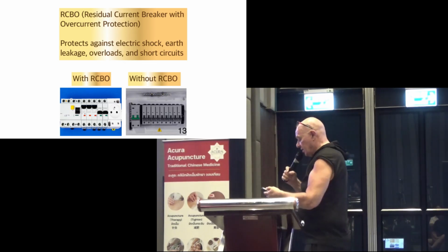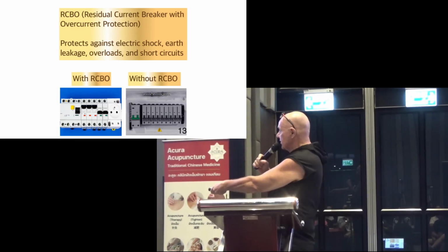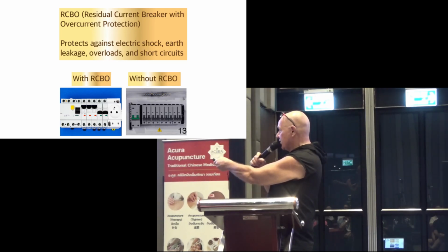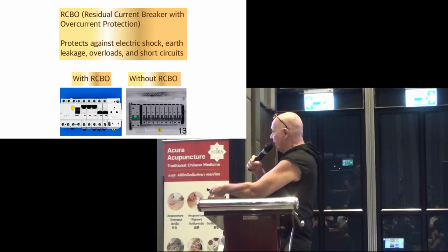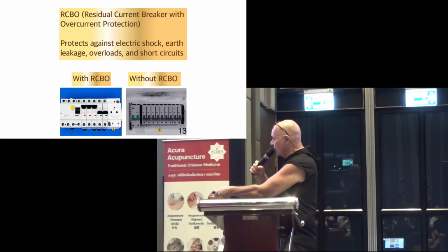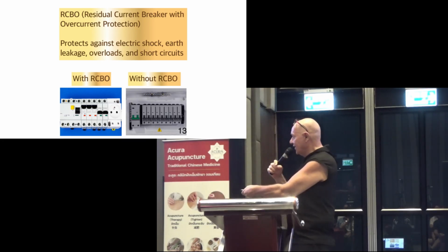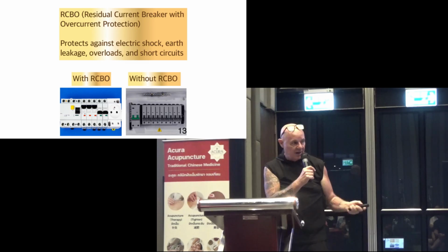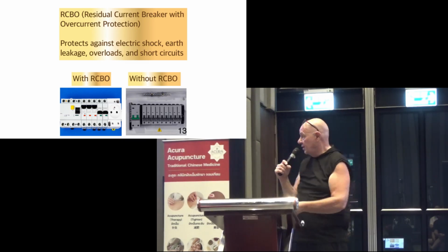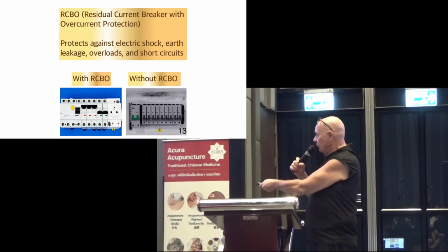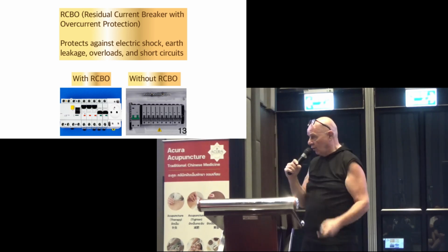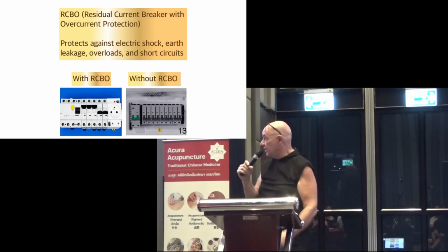That's a huge amount of power if that should go through you or try to get through you to earth. Okay, what do they do today? This is a distribution board with an RCBO - I'll come on to this as well, why it's important. This is a circuit breaker, and you know you have one because there's a test button with it. If you have this, it just has circuit breakers and earth leakage, which is good, because they will trip quicker than one of the old ones without any earth leakage whatsoever.